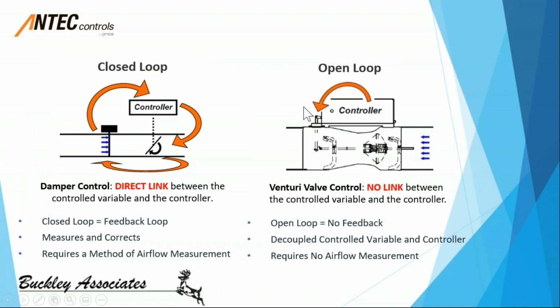So here's a look at both of these devices. When we talk about closed loops and open control loops, I think it's important to understand the differences between the two. With a closed control loop, there is always a direct link between the controlled variable, which for this application would be airflow, and the controller. What happens in a VAV box or any controlled loop system is that there is airflow through the box that is measured via some sort of sensor, pressure sensor, or transducer.